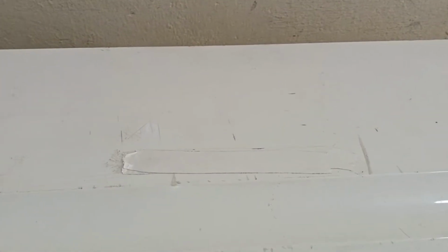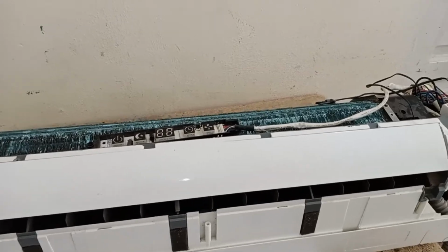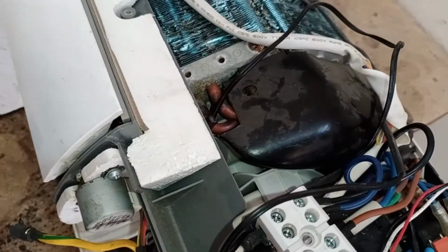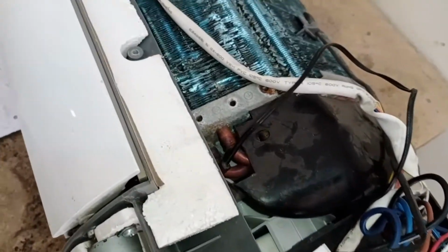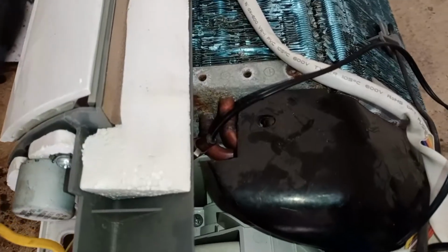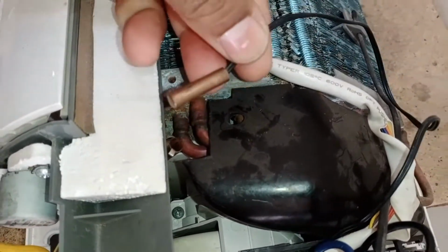This is also an indoor unit fault, so let's open the cover of the indoor unit and explain the issue to you. Now, once again, we have opened the unit because the E2 error is also related to the indoor unit. This error is also caused by a sensor fault, specifically the pipe coil sensor. If this sensor is not positioned correctly or not properly installed in its place, it can trigger the E2 error. Similarly, if the sensor is short-circuited or open, it will also show this error.